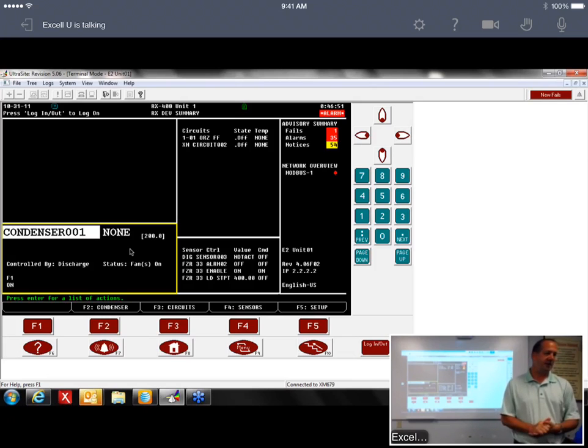It's not like the Echelon had a specific cable that you had to use. Modbus is not that way. It's RS-485 based, so it's not a special cable. But one of the things to remember is the polarity on a Modbus network. Anytime you're on a Modbus network and you connect it to E2, the polarity gets reversed.